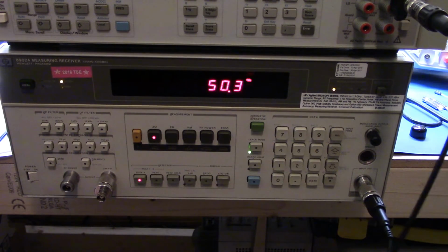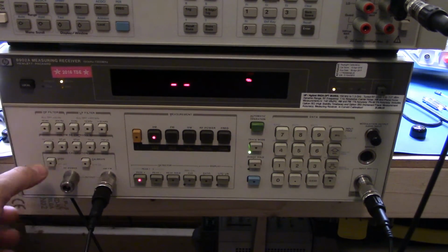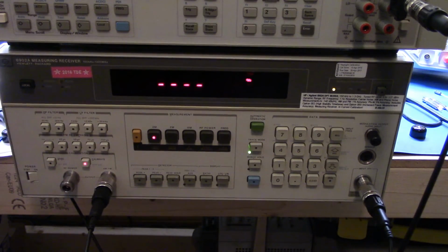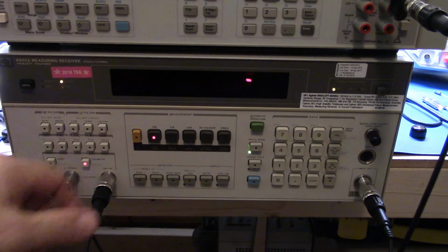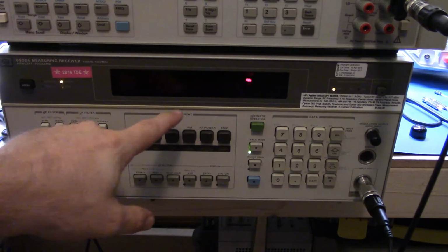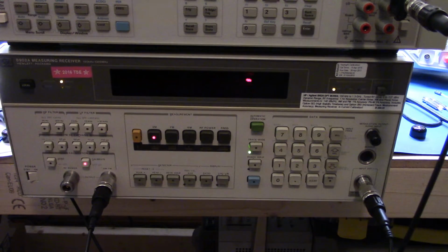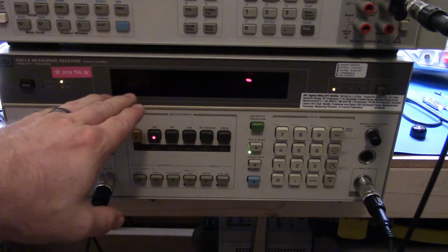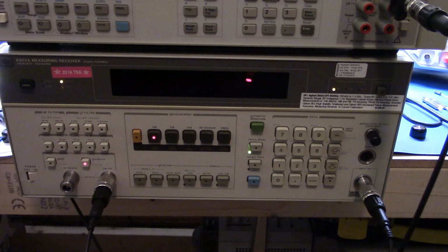Now, the other problem that is going on here is if I connect to the calibrator and I press calibrate, what it's supposed to do is find a signal out of the calibration port here, and then give me a value around 100%, showing what it's reading, and then I can calibrate that up. What you can see here is that nothing comes in. In fact, I wouldn't be surprised if in a bit we'll see an error 08 appear, which is telling me that there's something wrong with the calibrator. I need to check for it.